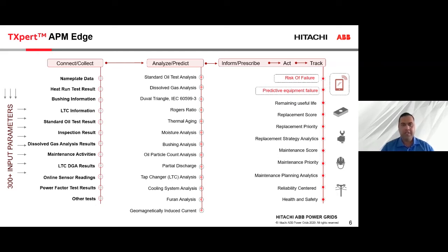So what we have done is we have quantified attribute data and made it discrete. Basically there are two data types. One is hard, solid numbers: suppose you do the DGA test, you get X ppm. But when you go for a visual inspection, you will just write down good or bad, yes or no. That data can now be part of this APM Edge platform, and we have discretized that based on our service experts.